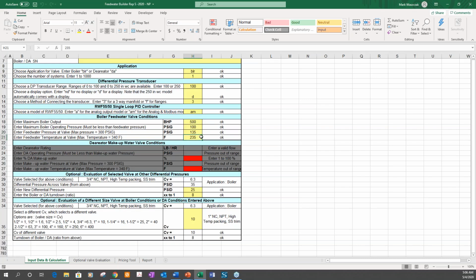So what this program does, it did select a valve for us. If you look down here, it selected a 3/4 inch valve. Now, you do have two options. The first option is evaluation of the selected valve at other differential pressures. What this means is currently our differential pressure is 35 pounds. Now, say we don't have 35 pounds. Say we only have 25 pounds because the inlet pressure to the feed water valve is only 125. Well, we'll put 25 in here.